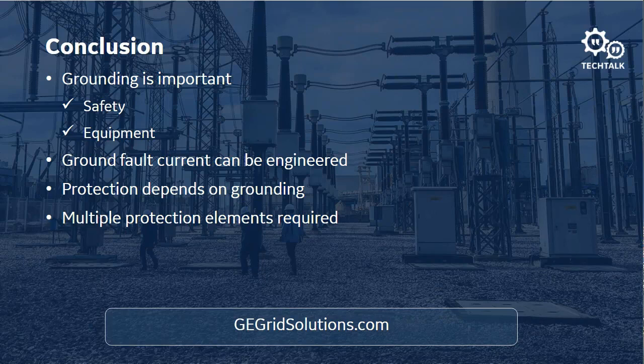In the high impedance method, we talked about a couple of voltage methods. One is just measuring the zero sequence voltage or the neutral voltage of the transformer, and it's an overvoltage. So if we have a ground fault, the zero sequence voltage will be elevated because the faulted phase will be zero and the unfaulted phases will be elevated. So we can easily detect that if the fault is not close to the generator neutral. If it's close to the generator neutral, we're not going to have enough zero sequence voltage developed to be able to detect it. So we need another method of detecting faults there.